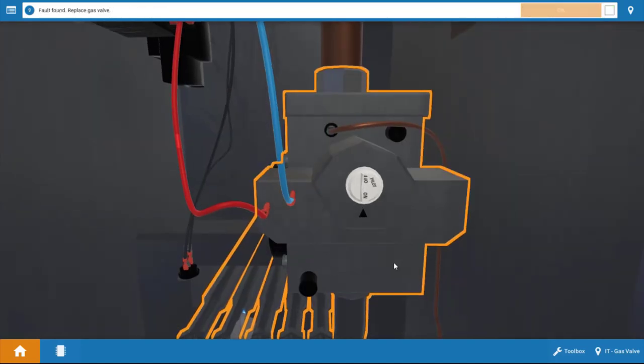What I want to show you on the gas valve is that normally before replacing it, even though we're pretty sure it's faulty, I would suggest always turning the power off, isolating the coil on the gas valve. In other words, disconnecting one of the wires, and then doing a resistance check across the gas valve coil to verify it's open.